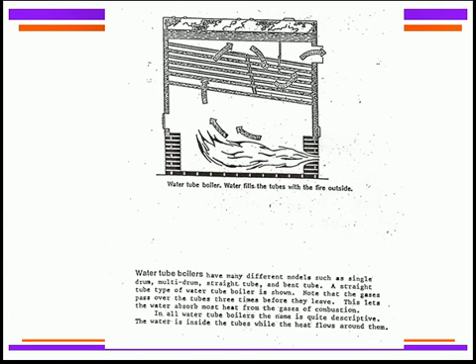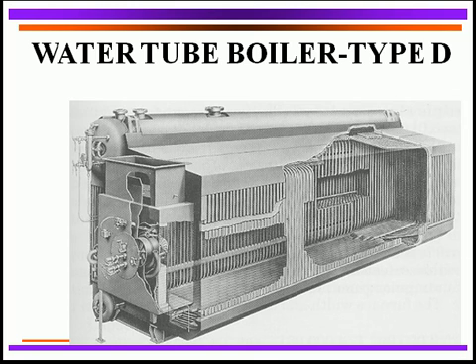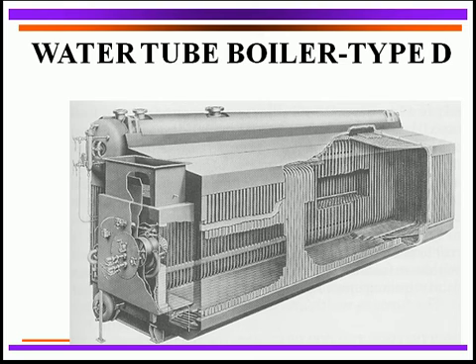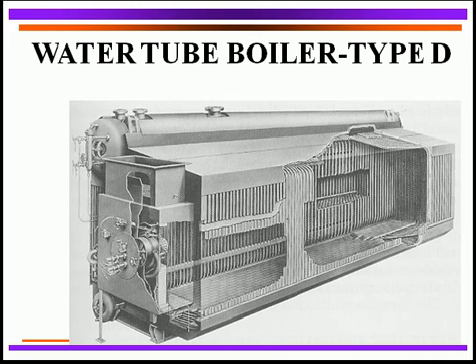The water tube boilers — exactly the opposite — the fire is on the outside of the tubes and the water is on the inside of the tubes. Here's a good example of a water tube boiler — what we call a Type D boiler. It's designated D because in the upper left-hand corner we have what we call a steam drum — that's where our feed water comes in and where our steam production actually occurs. We also have another drum at the bottom left-hand corner known as the mud drum. That's where a lot of our sediment and sludge accumulates and that's where we blow it down from. The configuration of the boiler tubes gives us what looks like a Type D design, so that's why they call it a Type D boiler.